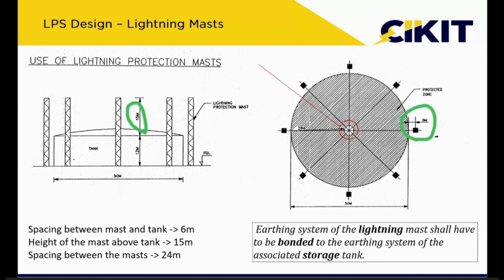And here also, at every 24 meters we have to provide one air terminal. If we keep it like this, the protection provided by this method will be almost similar to the protection provided by the previous method. In this method also, if you observe, the center portion is still unprotected. So this is a drawback of these two methodologies. And the standard has highlighted that the earthing of the lightning protection mast can be bonded with the tank body earthing.